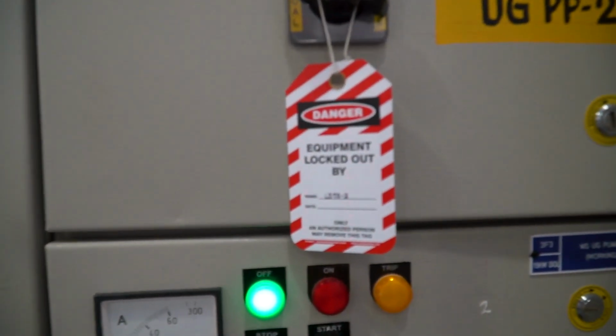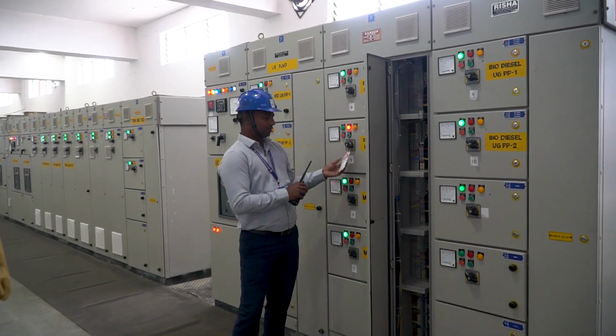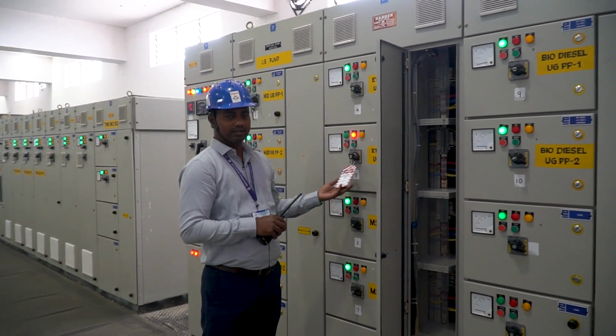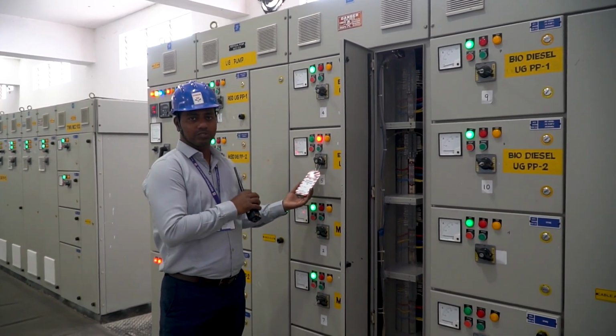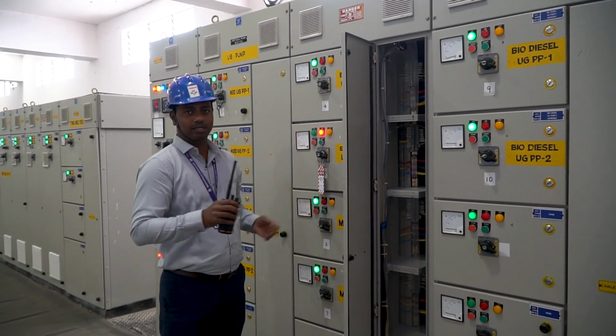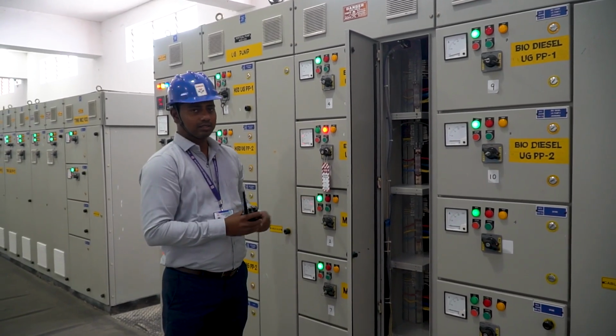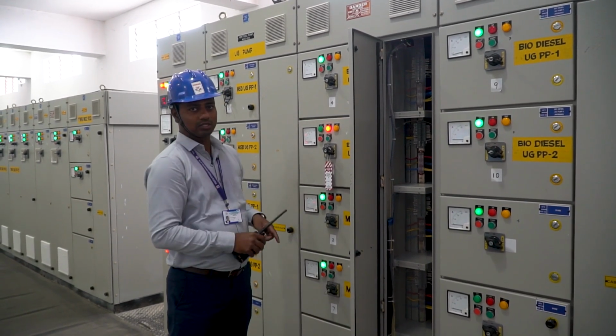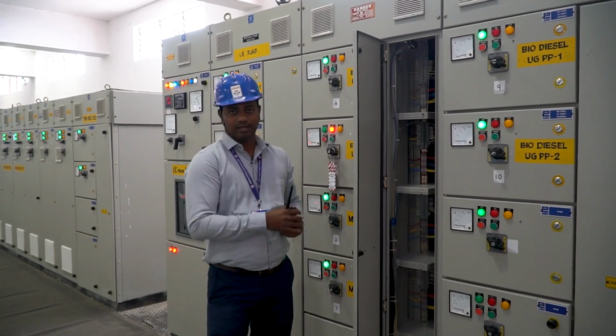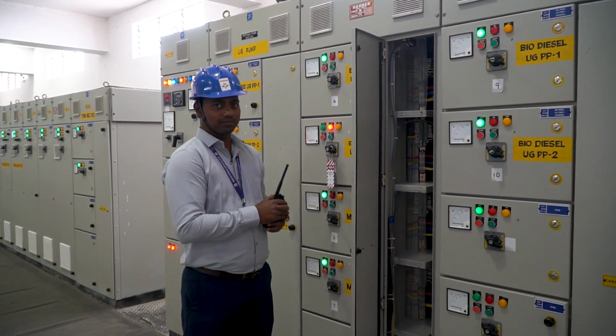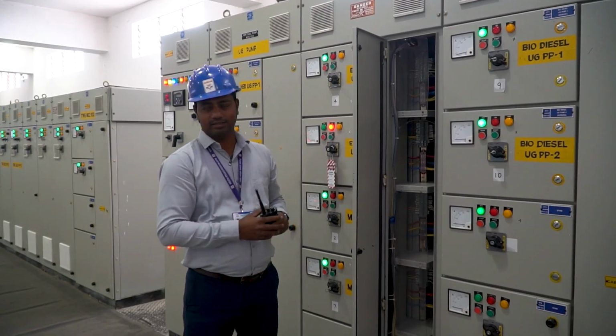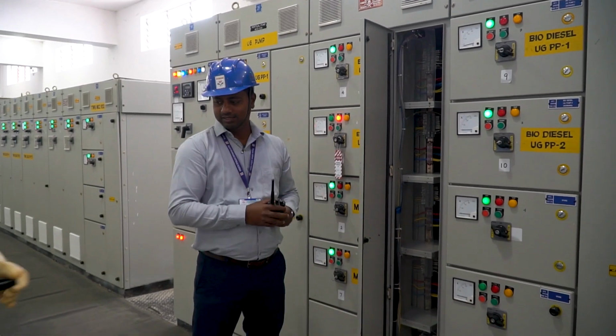Here, if you see, this is the LOTO tag. This LOTO tag mentions that this equipment is isolated. So once the tag is put, it means no electrician will be working on this thing. So now this panel is isolated. Now we can check the current and voltage level being injected from this panel, since this panel is under maintenance. Electrician will be doing the job.